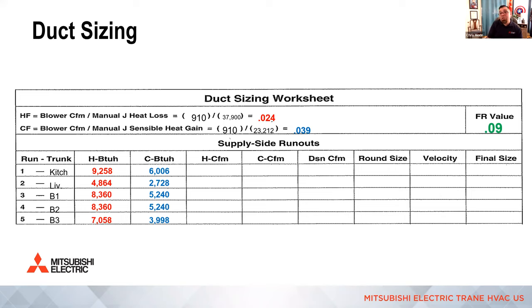The other alternative was we could go back through design instead of running at a 0.5 static pressure to start with, maybe 0.3, which is our low static option, but then we don't have the ability of turning it down. Remember, we always want the ability for our technicians to turn it up or down. So that's why we design around a medium speed and medium friction loss. I'm sorry, medium static pressure. I don't want to confuse it too. Hopefully that answered your question.